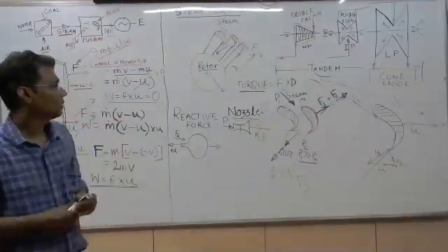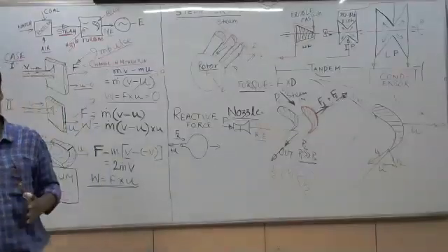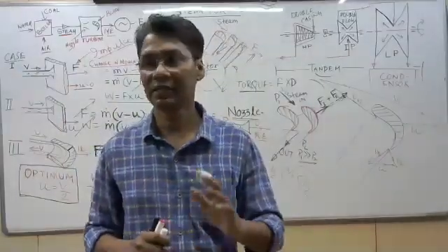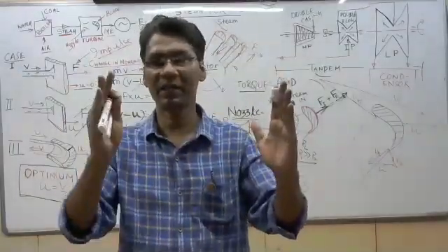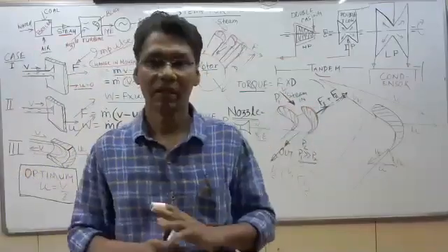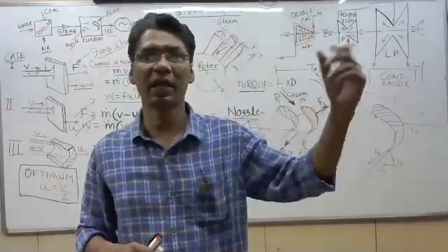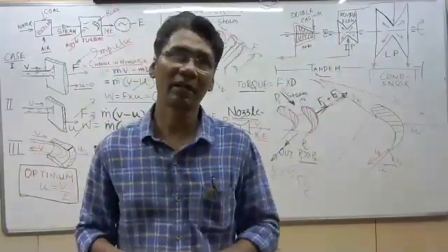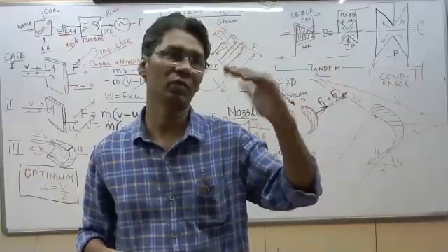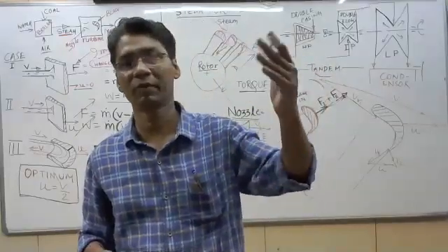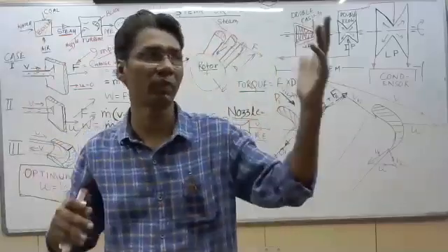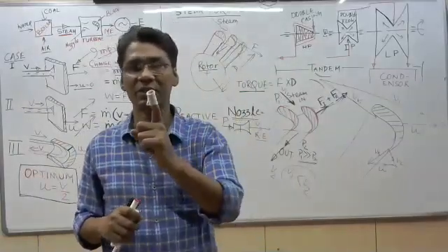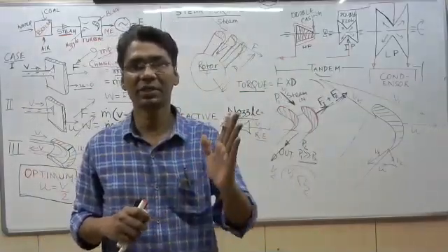So now in a power plant, turbines are mainly used in three sections, that is HP turbine, IP turbine and LP turbine. Earlier there was a single turbine, HPLP or IPLP, in a single block, but for larger turbines, such as 60 megawatt, 200, 210, 250, 500, 800, 1000 megawatts, we have the three-cylinder type: HP cylinder, IP cylinder and LP cylinder.